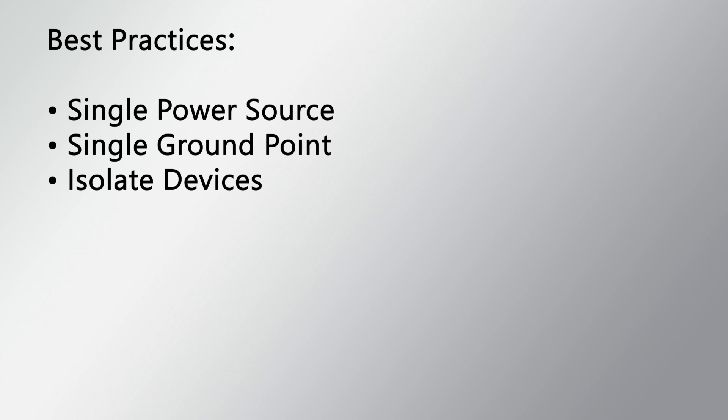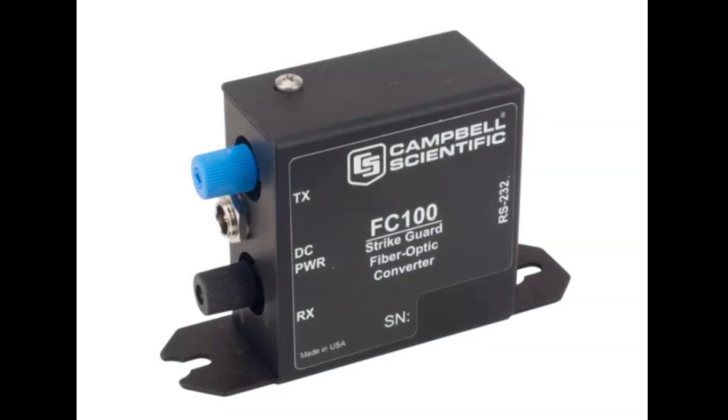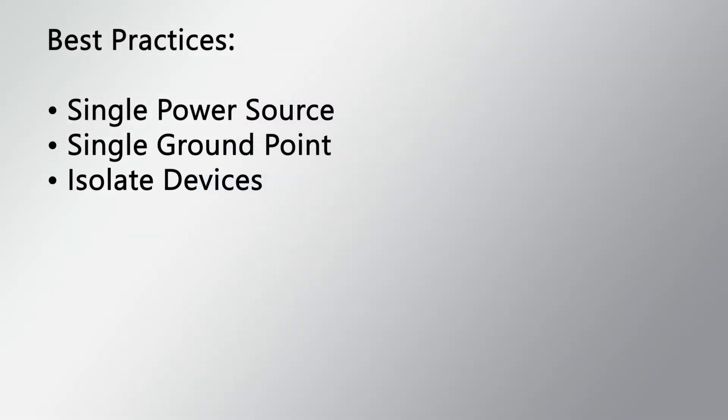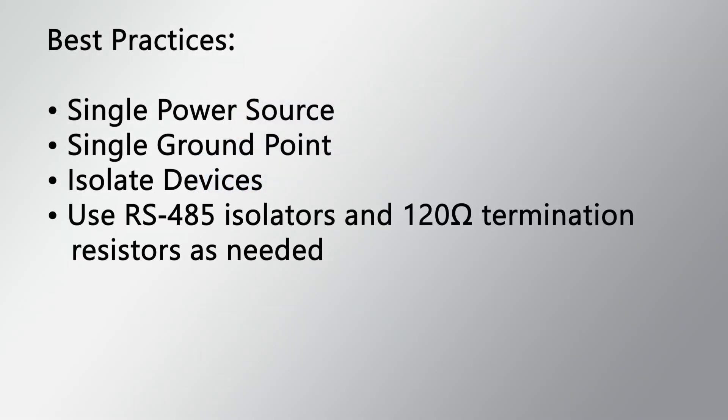Use optical isolation devices, such as the FC100, for communication devices when needed. Use RS-485 isolators and 120 ohm termination resistors as needed.